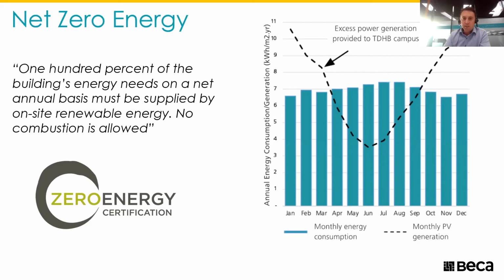And again, what's interesting is that we optimized the building pretty much as we could with a lot of computer modeling, but there's still around about 40% of the annual energy use for the RO plant, which is very little we could actually do about, reusing existing RO plant for reverse osmosis water. But it does still show that you can achieve net zero energy. It won't be as straightforward for every healthcare project, but it is possible, taking into account high energy use for healthcare buildings.